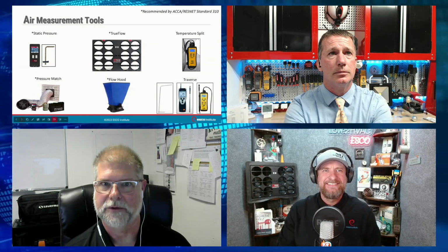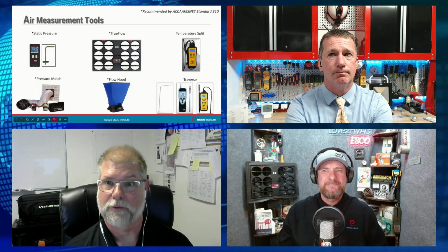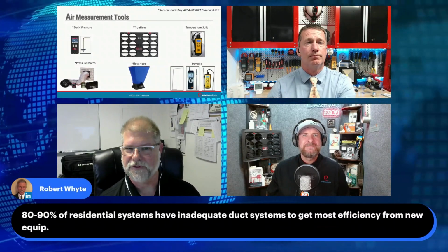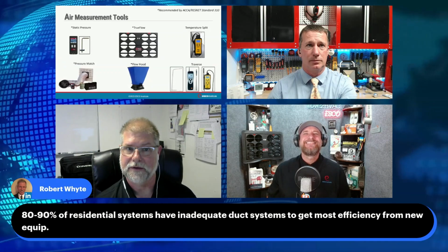Something that Ty pointed out, I guess probably about a year ago, was that many professionals were using static pressure as a silver bullet, and they were taking it out of context, and they were trying to make it mean more than what it really did. And so I think one of the things we have to keep in mind is every measurement that we take should have a purpose, and we need to be looking for an intended outcome from that to help us troubleshoot a system and then understand how to explain it in terms that an average homeowner can understand.